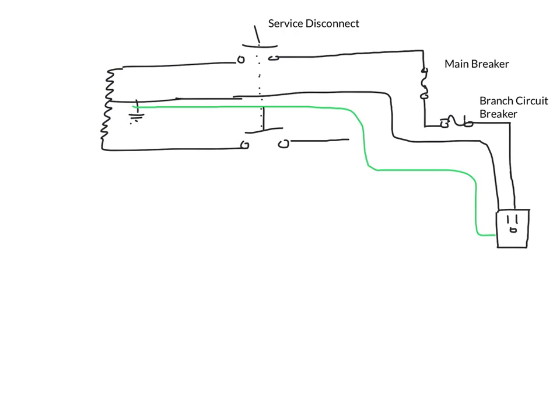The only thing that can be considered grounding in this circuit is the actual conductor that's connected to the grounding electrode. The point of grounding in a circuit is to stabilize voltages. It's to give a reference point for the transformer so that there's essentially a zero mark from where voltage knows to go up or down.